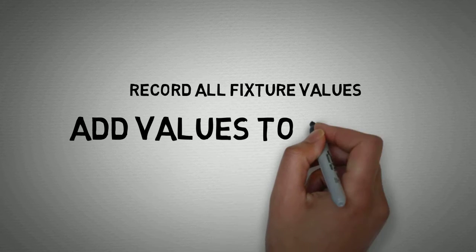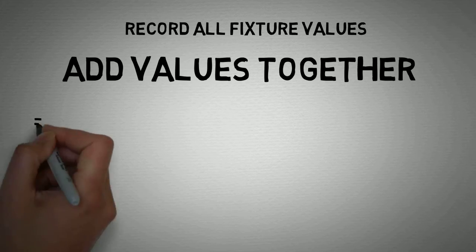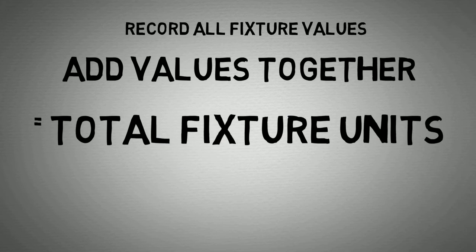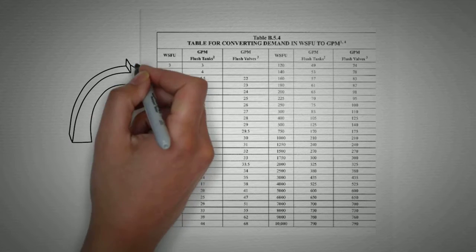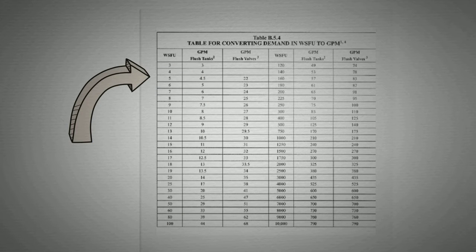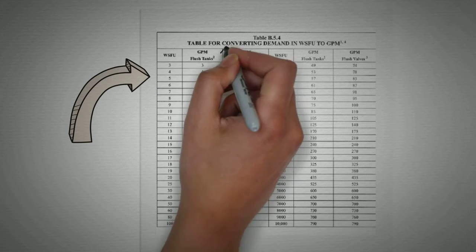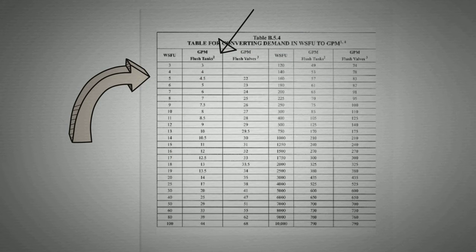Add the values together and round to the nearest whole number to obtain total fixture units. Finally, refer to the NSPC's Table for Converting Demand in WSFU to GPM chart and simply match the total number of water supply fixture units to the given value in GPM.